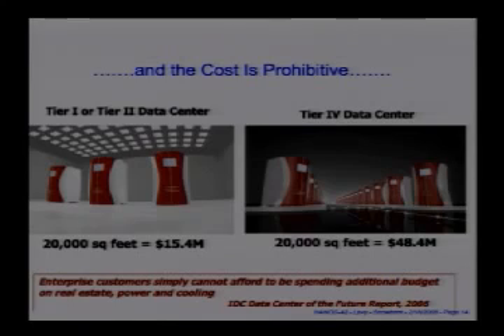Now, that's not if you picked it up on the market after the fact for pennies on the dollar because somebody went bankrupt — this is truly building it, say in an existing warehouse: 20,000 square feet of tier 4 data center that's going to be up no matter what. That's 5 nines, or even 100% SLAs — N plus 1 plus 1, or 2N plus 1, or 4N, or whatever you want to make it — really high-end redundancy from the Uptime Institute standards. That comes to 48.4 million for 20,000 square feet. That's a big difference, isn't it?